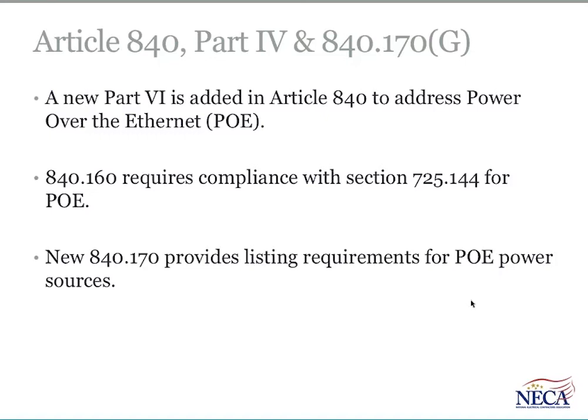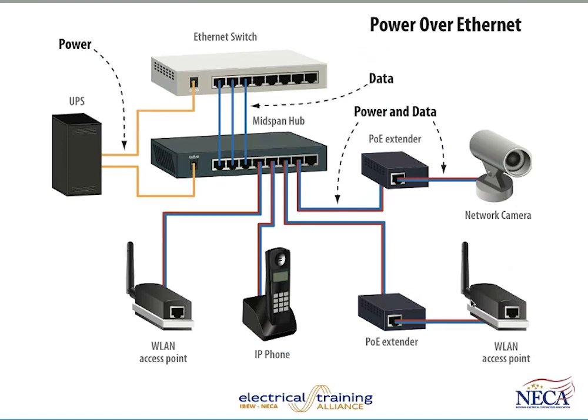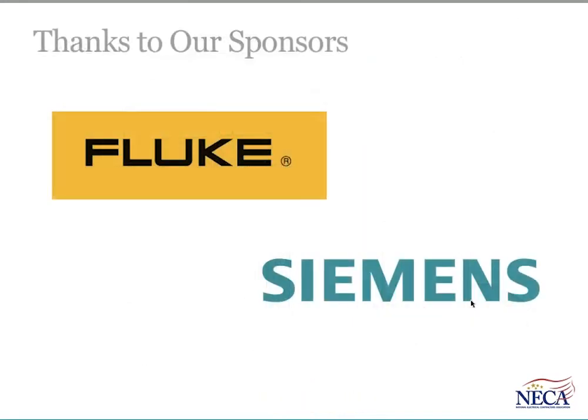This is not something that's new, but it's actually seeing expanded use, and the NEC has to be equipped to address installations where not only are we running Ethernet that is used for data and communications, but in some cases within the same cable we will be sending power to the various devices in our system and powering them up through that same cable. So that's what's meant by power over Ethernet. You can see the various devices here, whether it's a camera or other type of device. But not only are we sending the communications and signaling circuits to it, but we're also including power to drive the device itself. So that's what we have.